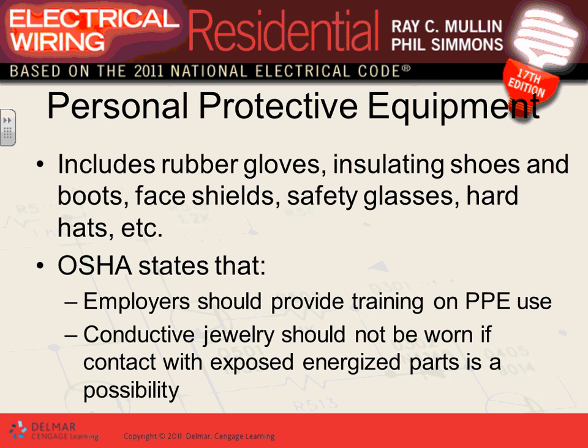When you work on equipment energized, personal protective equipment, PPE, is a big deal - clothes, gloves, hats, and so forth to protect you from two hazards. Number one is the shock hazard, like grabbing an energized 4,000 amp bus. Number two is the arc flash hazard - you're working on an energized object, you drop a bolt or wrench inside the switchgear, and a big ball of fire, an explosion happens, and that fire engulfs you.